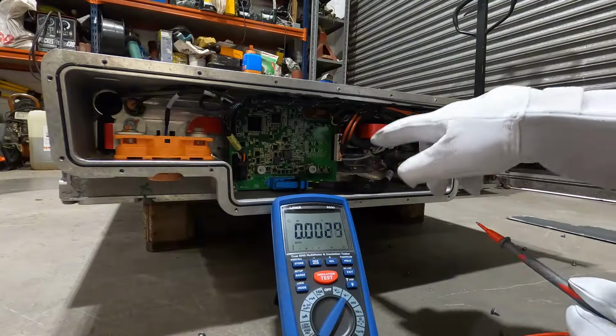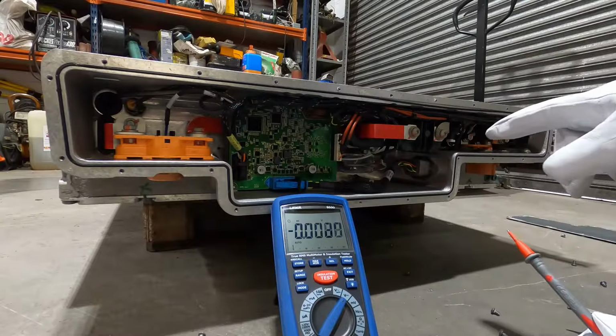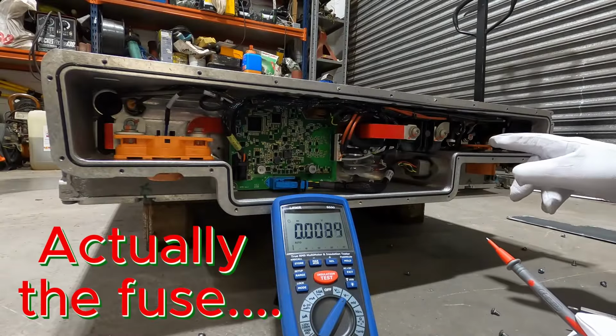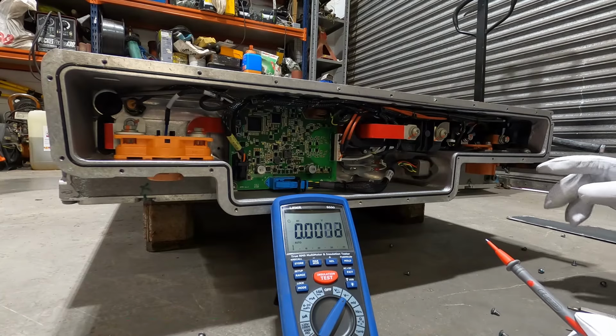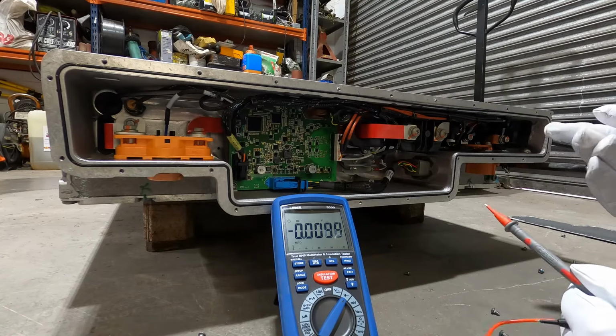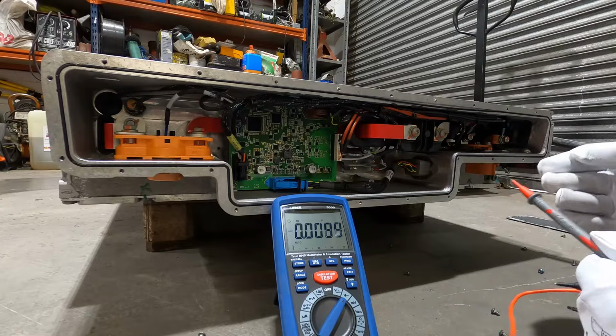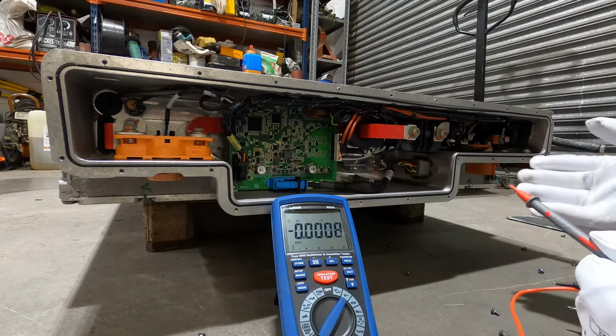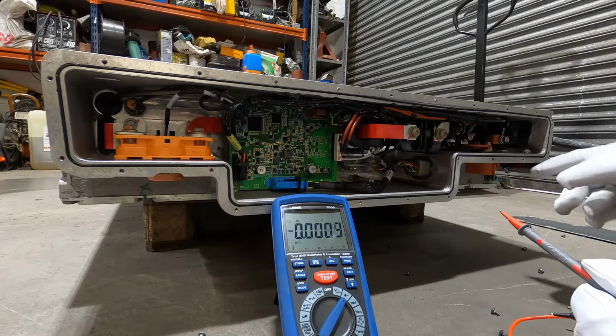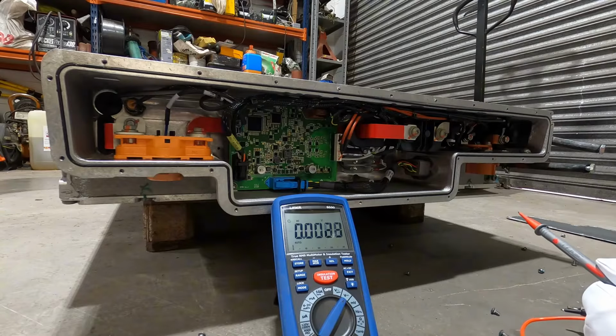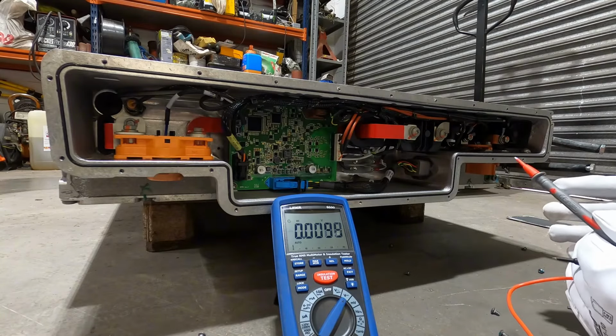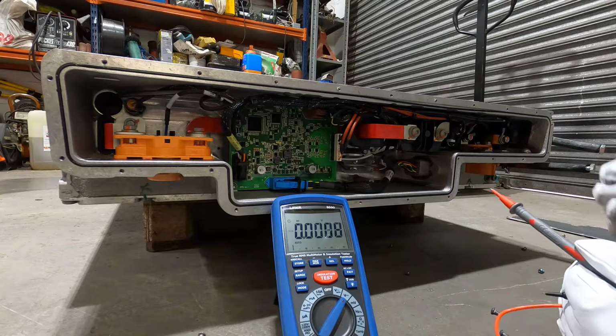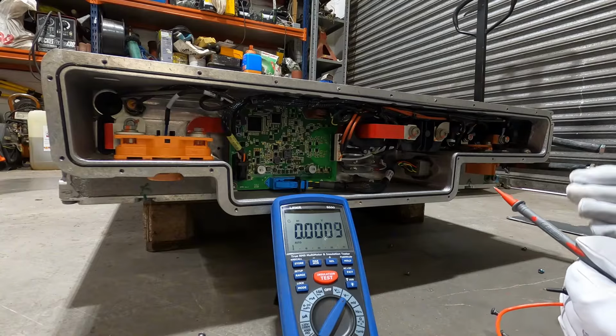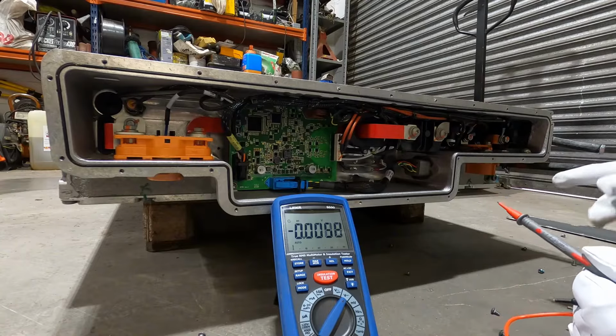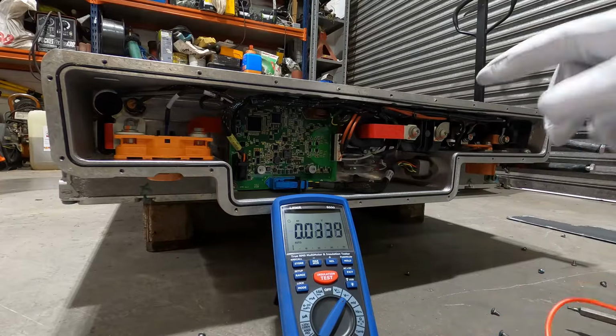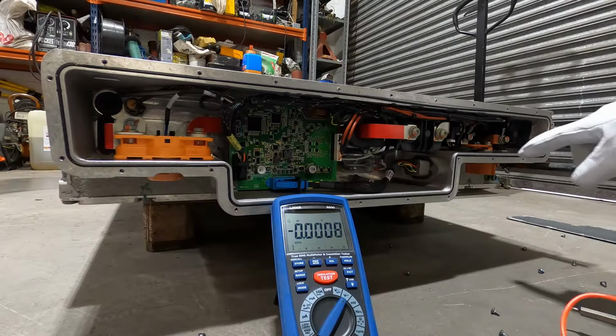Bus bar comes around through there, into a big contactor. You've got a secondary contactor there that might possibly be a pre-charge relay, and what that essentially does is open up, using a resistor, a smaller amount of voltage to go to the actual inverter to charge the capacitors up. If you put full pack voltage straight to a capacitor, you're basically going to kill them fairly quickly, and so it goes through to your little pre-charge one instead.